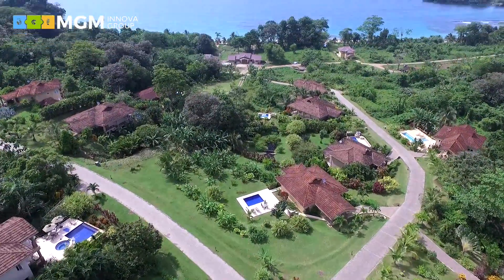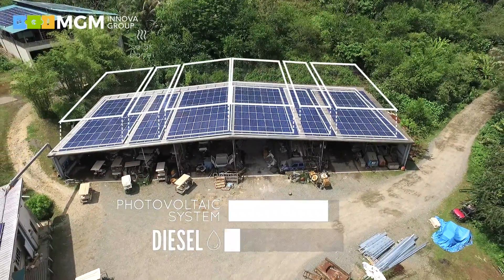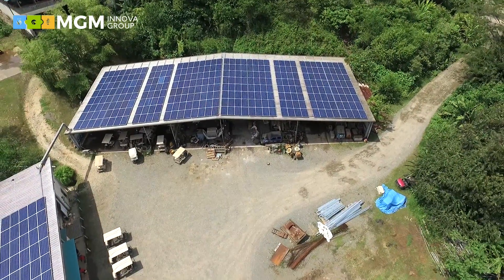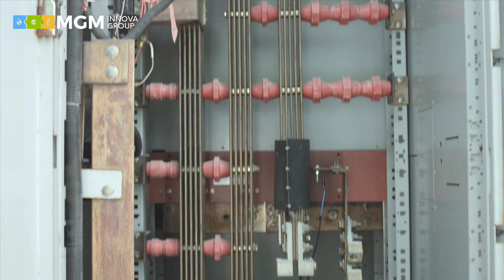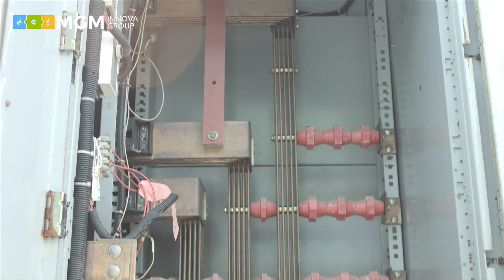The energy generated by the photovoltaic system leads to a reduction in the consumption of diesel, which is currently used to generate electricity through motor generators. The entire power generation system is controlled by the Fuel Save Controller by SMA, which, depending on the energy demand of the resort, increases or decreases the energy supply from the diesel generators — in all cases prioritizing the use of the photovoltaic system.